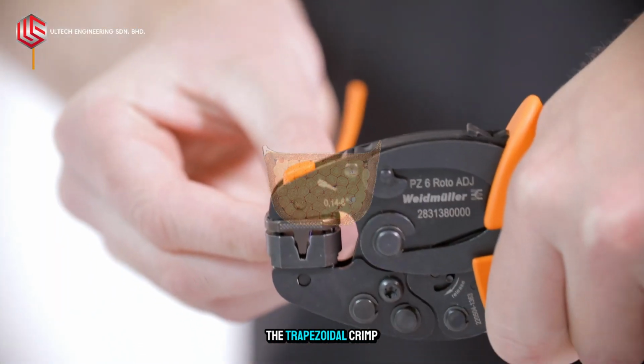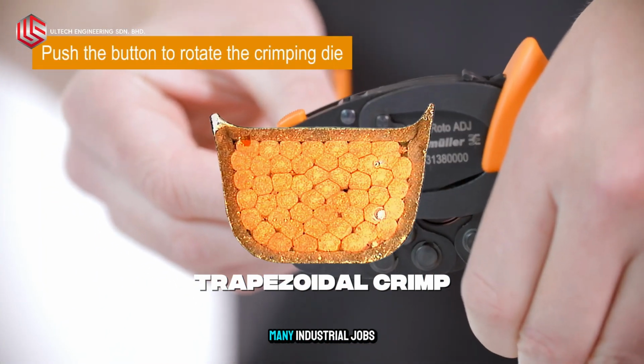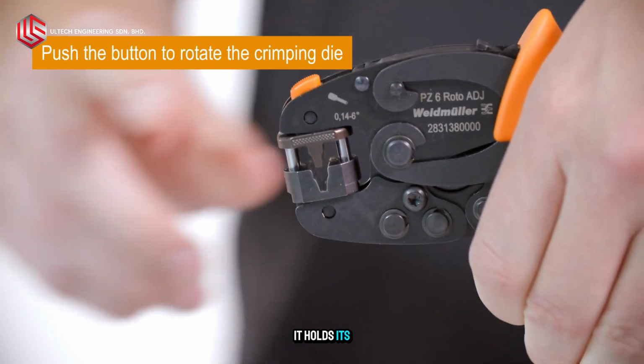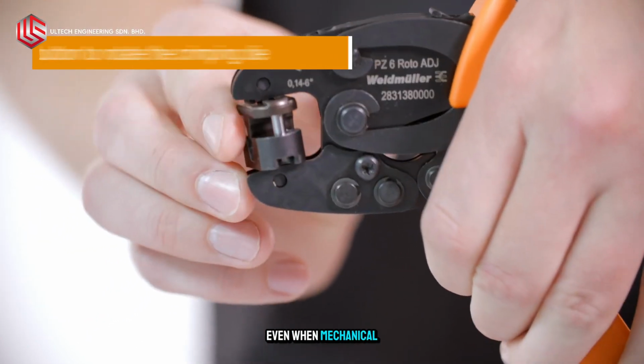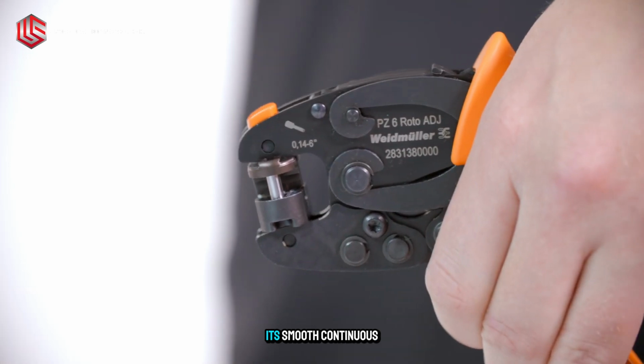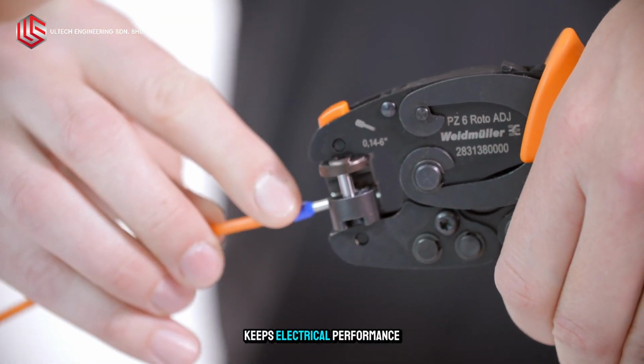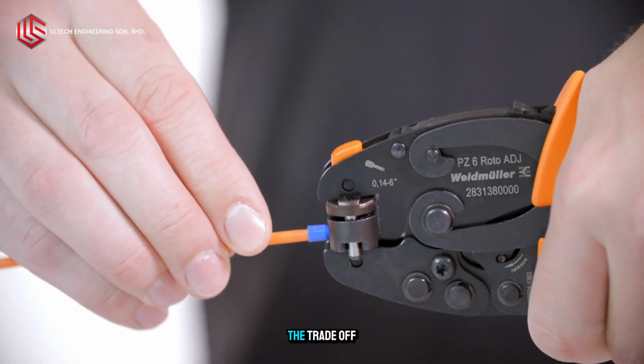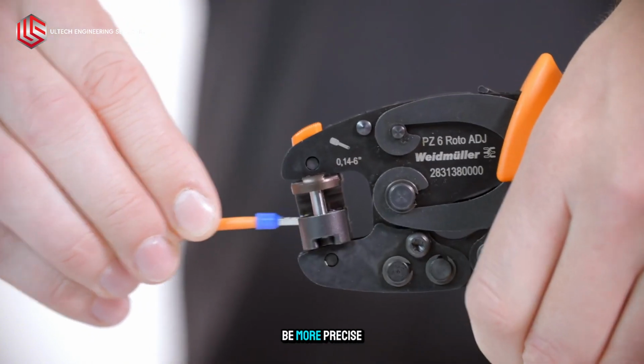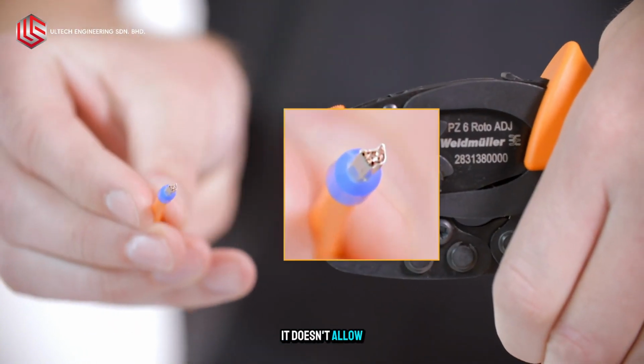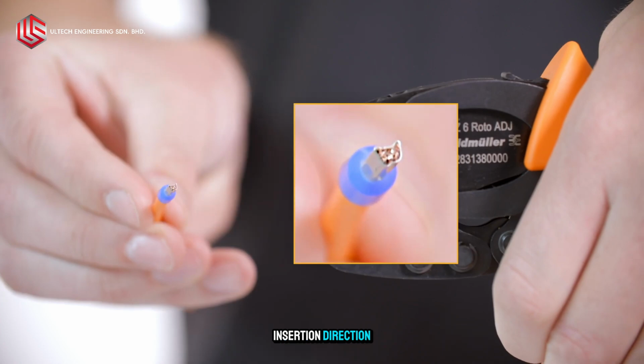Let's start with the trapezoidal crimp, a favorite for many industrial jobs. It holds its shape under load, even when mechanical or thermal stress is high, and its smooth, continuous surface keeps electrical performance consistent. The trade-off: you've got to be more precise when positioning. It doesn't allow for a neutral insertion direction.